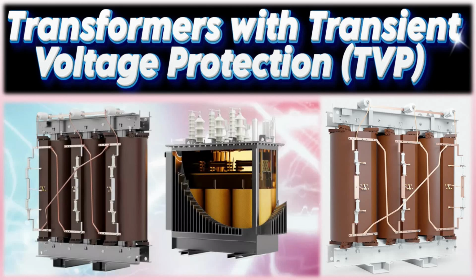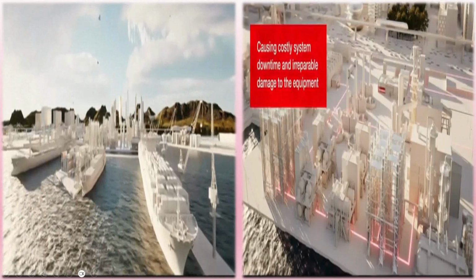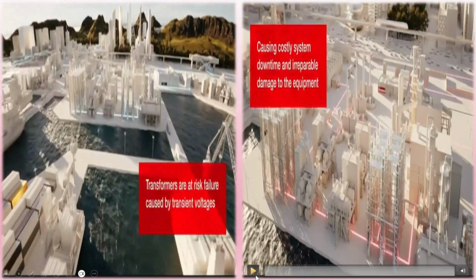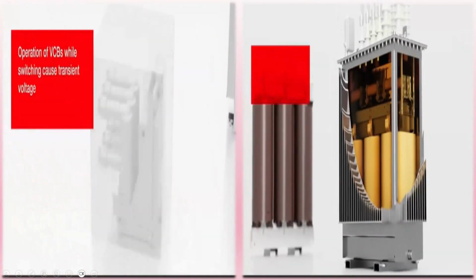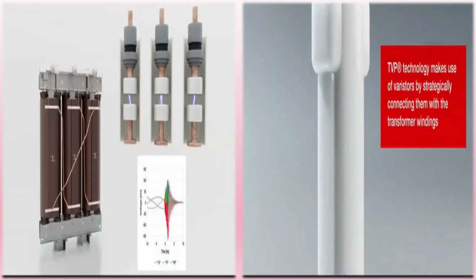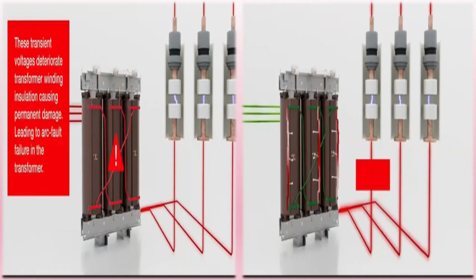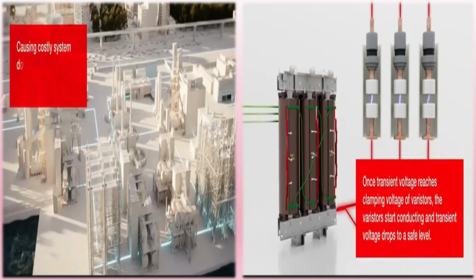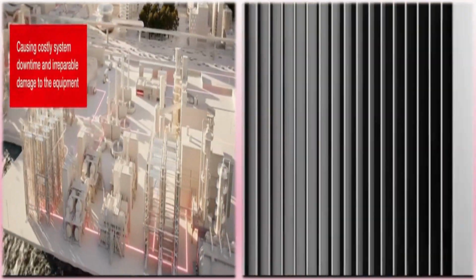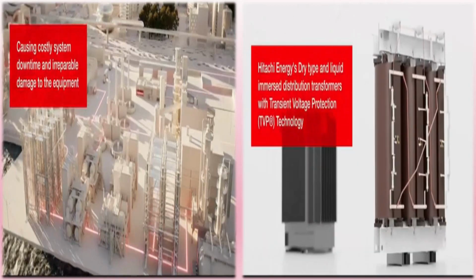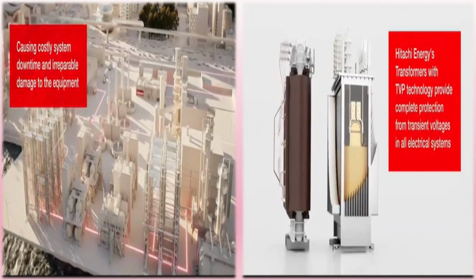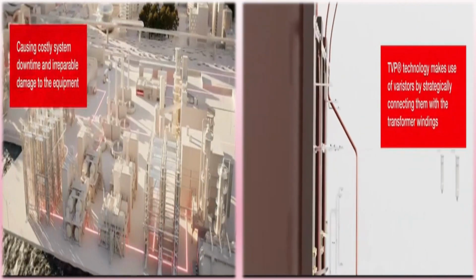In modern power systems, the reliability and longevity of electrical equipment are paramount. One of the most critical components in the distribution network is the transformer, which is vulnerable to a specific type of electrical disturbance known as fast transient overvoltages. These transients, often caused by switching operations involving vacuum circuit breakers (VCBs) or SF6 breakers, can lead to insulation breakdown, winding damage, and ultimately transformer failure.